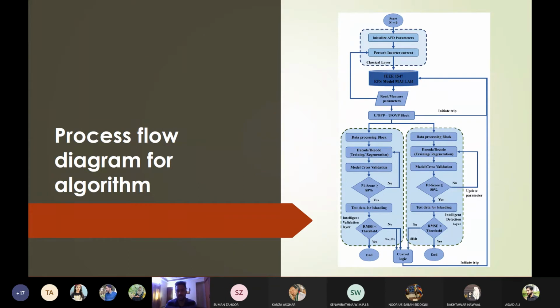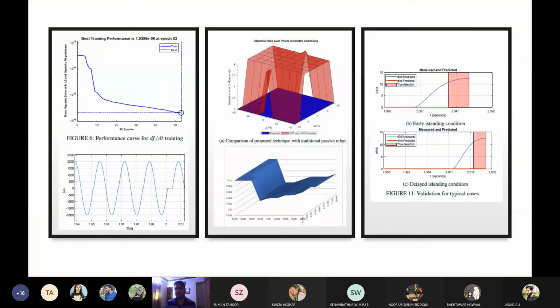One loop works on the rate of change of frequency, and the other works on the principle of phase angles. They validate each other — if one detects and the other doesn't, it signals that something is fishy. If both operate, there's a control logic to act on it, which shows our detection algorithm is quite sophisticated.